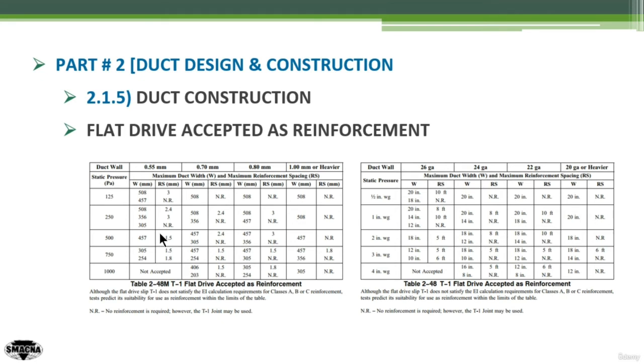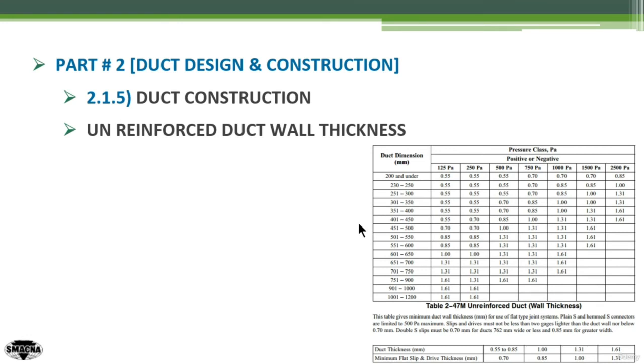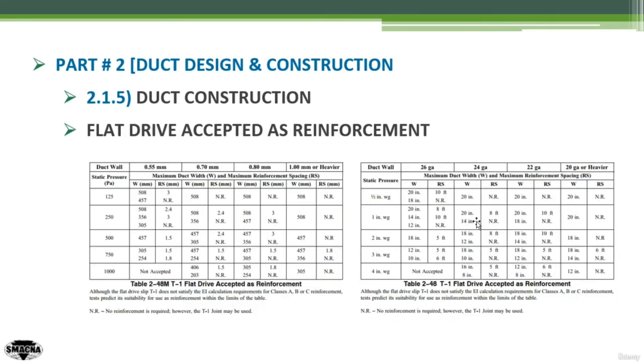Let's choose another duct randomly. This duct is at an operating pressure of 250 Pascal and is 450 mm. Going back to the previous table to specify the sheet metal thickness — 450 mm lies in the duct dimension range from 401 to 450. The intersection of the 250 Pascal column with the 401–450 row gives a duct sheet metal thickness of 0.7 mm. Going to the next table, 0.7 mm at 250 Pascal gives a maximum duct width of 508 mm and a maximum reinforcement spacing of 2.4 m.